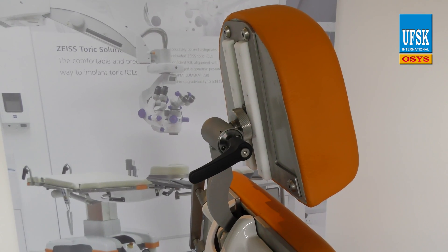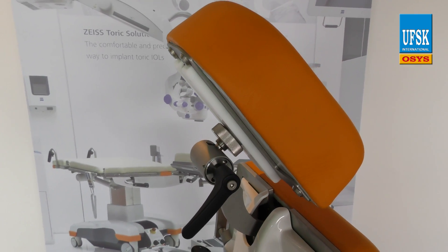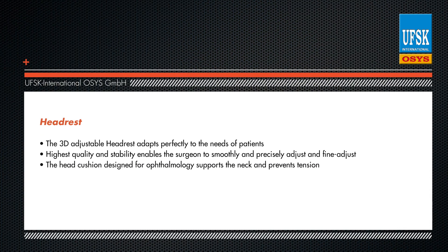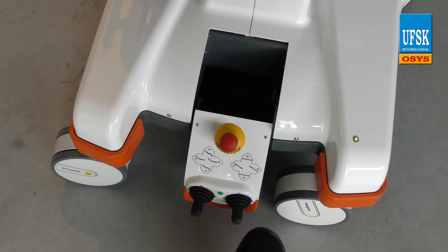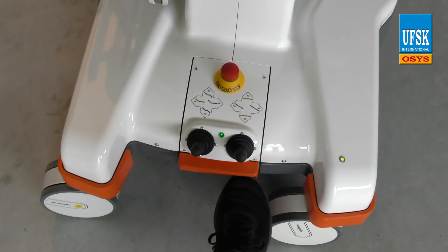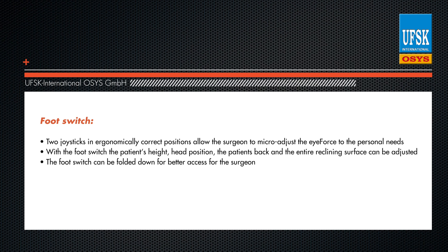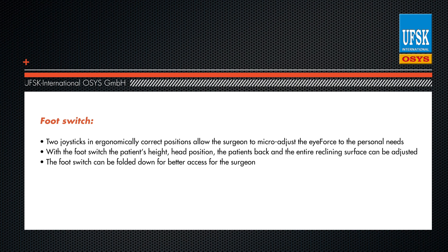The surgeon can adjust and fine-tune the patient's head position without effort, thanks to the superior quality and mechanical stability of the headrest element. Two joysticks in ergonomically correct positions allow the surgeon to micro-adjust the eyeForce to his or her personal needs. The foot switch, which can be folded down for better access, allows you to adjust not only the patient's height and head position, but also the patient's back and the entire reclining surface.